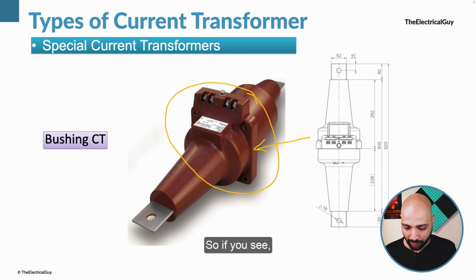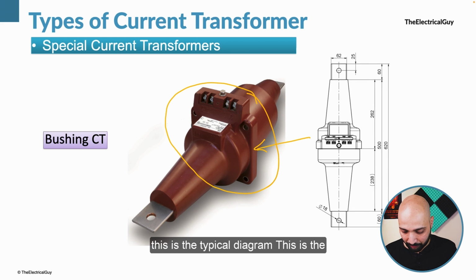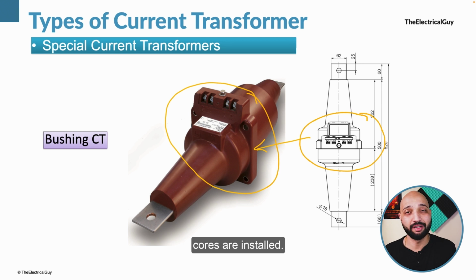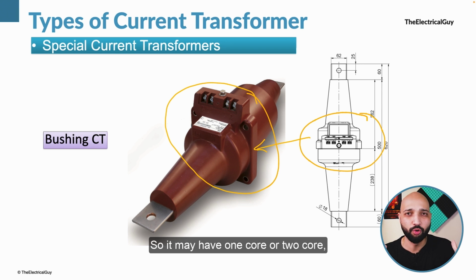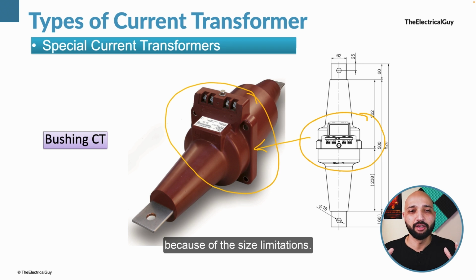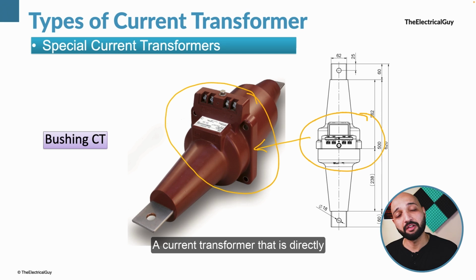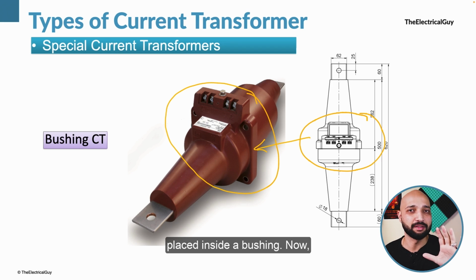If you see, this is the typical diagram. This is the center portion where the cores are installed. It may have one core or two cores, but it cannot have more than that because of the size limitations. For smaller cases, when we go to high and extra high voltage, of course, there is the possibility of having more cores as well, right? So that is the bushing current transformer, a current transformer that is directly placed inside a bushing.